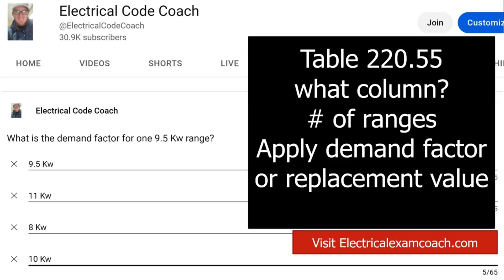Now that we've found what column we're working from, we're going to start on the left-hand side and find our number of appliances, then come across and tee off with that Column C value. So: what column am I in, find my number of ranges, then either apply your demand factor — which is columns A and B — or find your replacement value, which is in Column C. In this case, the answer is 8 kW.